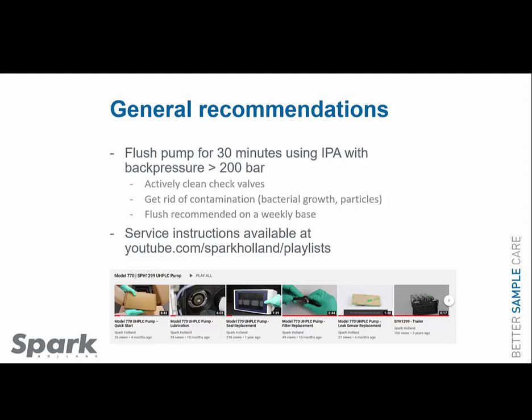We would like to provide you some general recommendations. Please flush the pump for 30 minutes using 100% IPA with a back pressure of at least 200 bars. This will actively clean the check valves. It will get rid of any contamination inside the pump flow path, like bacterial growth and particles. We recommend to flush this on a weekly basis. Please watch our service instructions, which are available on our Spark Holland YouTube channel.